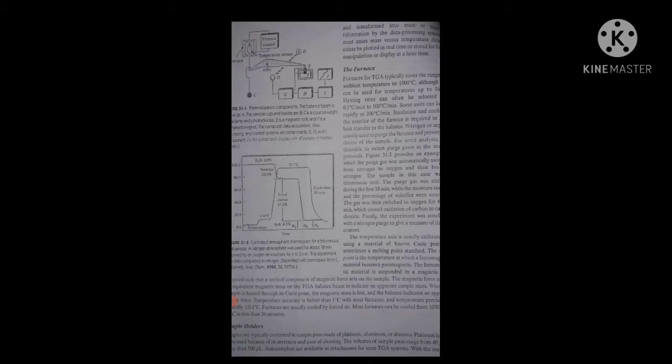This is the third part of TGA: the sample holder, in which the sample is contained. These are the pans which are mainly made up of platinum or aluminum. Platinum is most often used for two reasons: one, it is inert, and the other is easy cleaning.